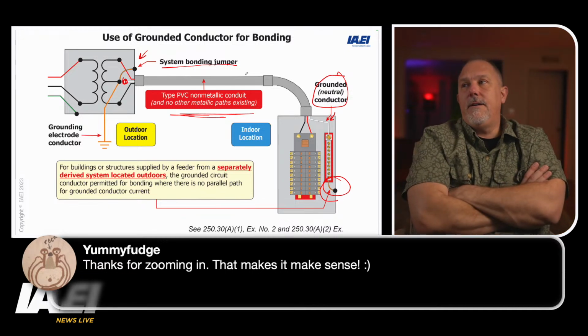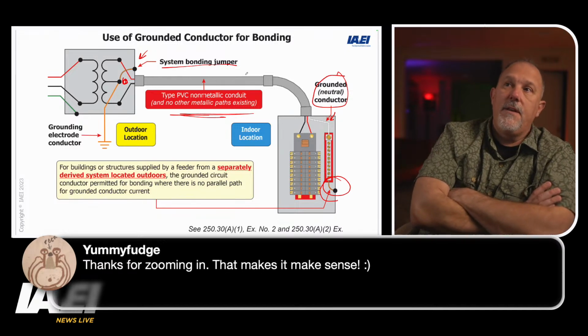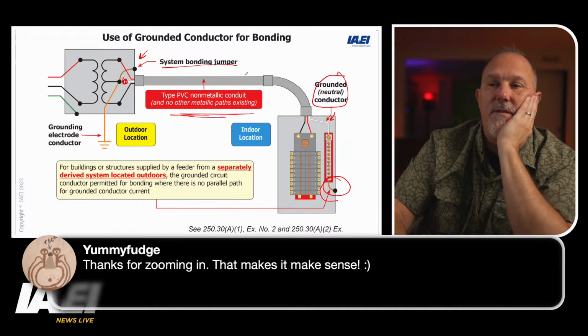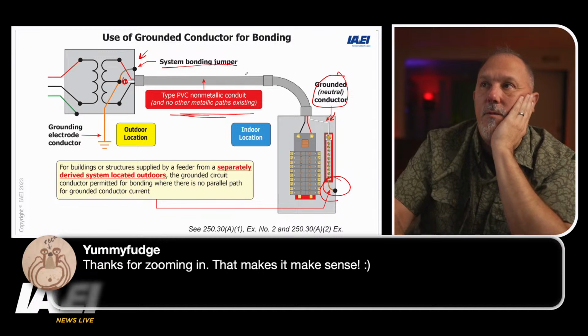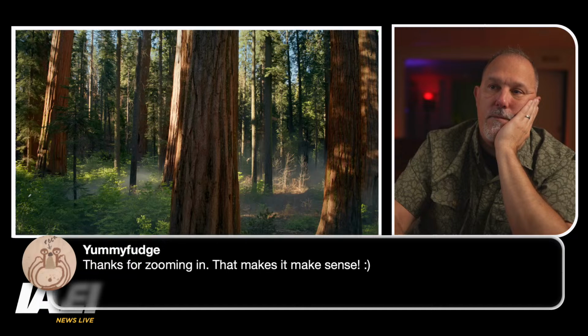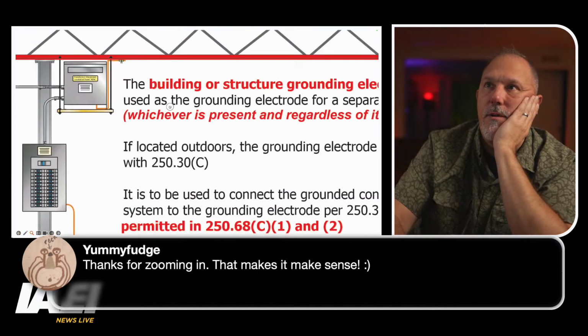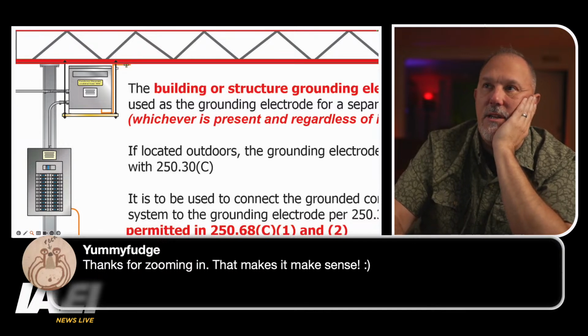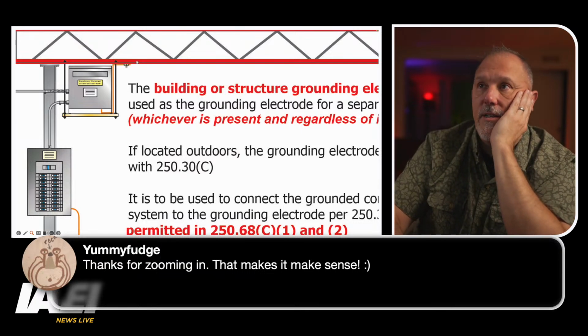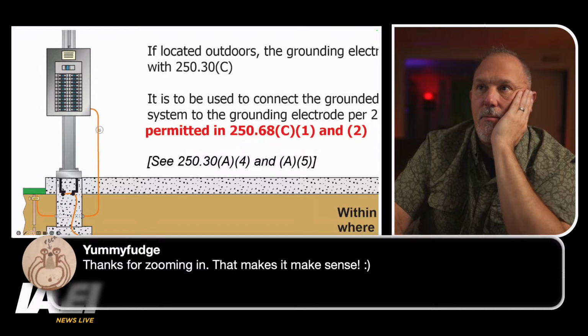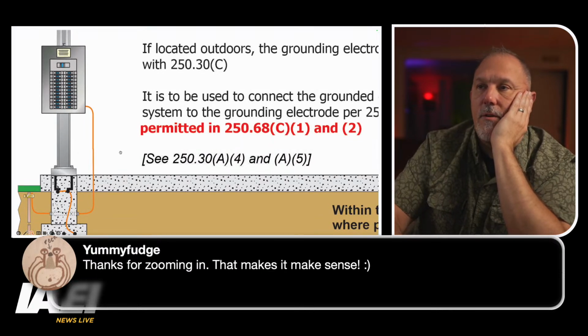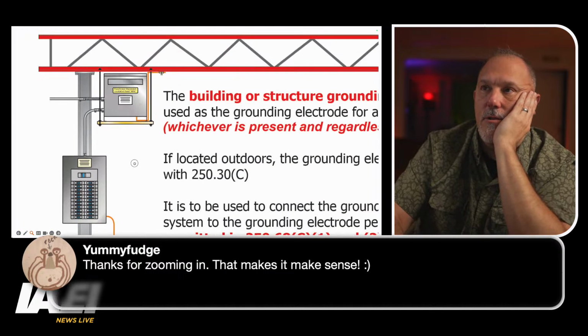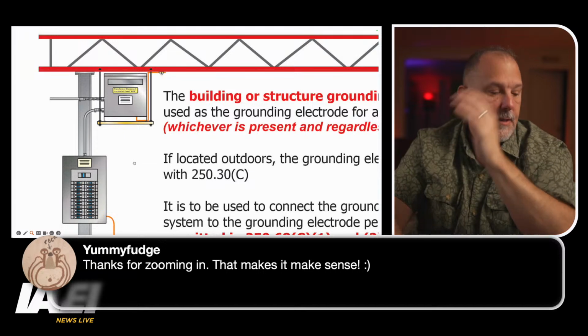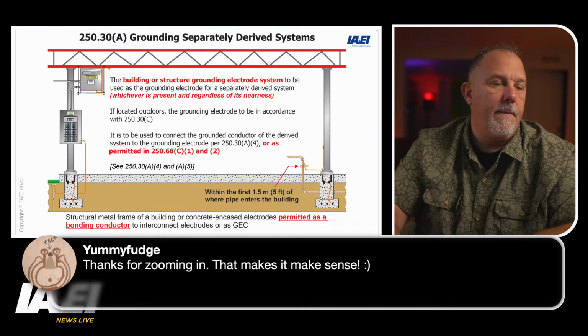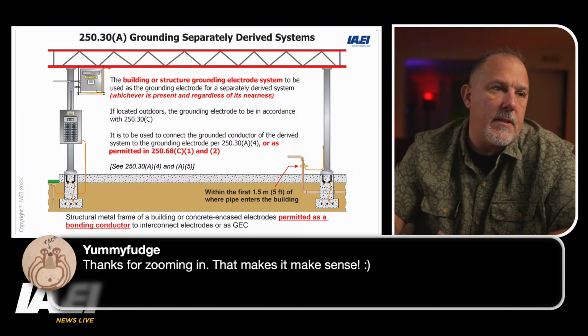Now this one here, you see how they did this? And this is what I believe we were talking about earlier. They bonded with the building steel for this separately derived system up here in the corner. There's no ground rod there, right? So that is how they did their bonding in that application. And then for this panel board, they bonded with the grounding electrode system as well, because the building steel, etc., is your connection point. That's what I would have expected. That's what we typically see. We don't typically see a ground rod being used.